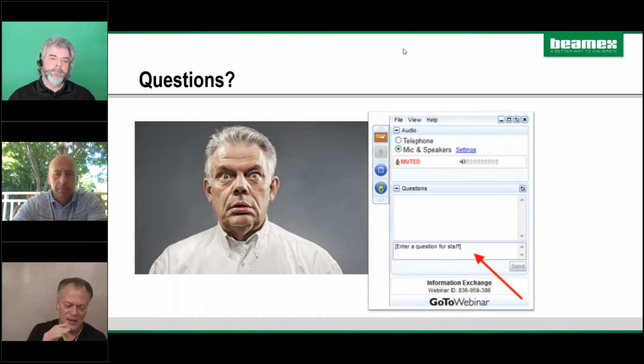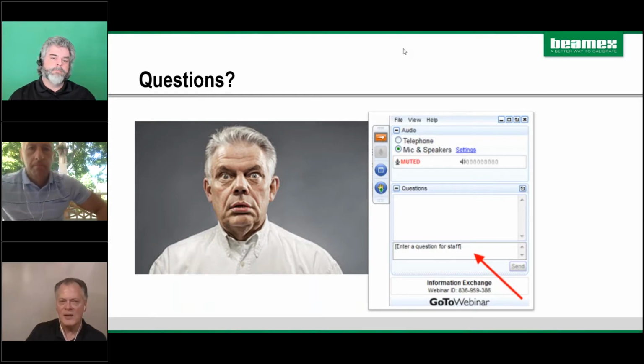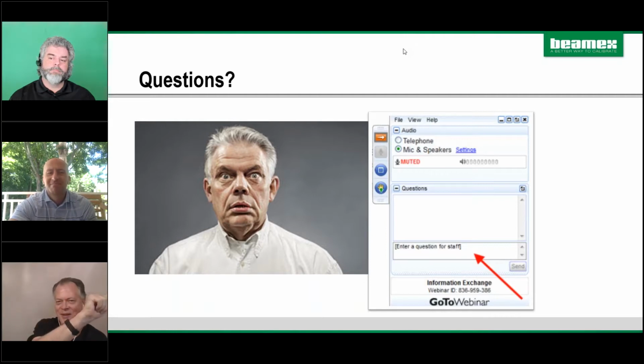And I say the best way is to document. You don't need to document everything, but if these things are really critical, compare where you are today to 6 months down the road, 12 months down the road. Bottom line is you have random noise, so when things drift, sometimes they're up, sometimes they're down for ambient conditions. But if you're seeing a trend going in an upward direction every time you go out, you can kind of predict and look at your interval to see whether you need to go out every 6 months before it's out of control, or can it go 2 years. I think in general people over calibrate, they go out too often, and so by documenting you can kind of optimize.